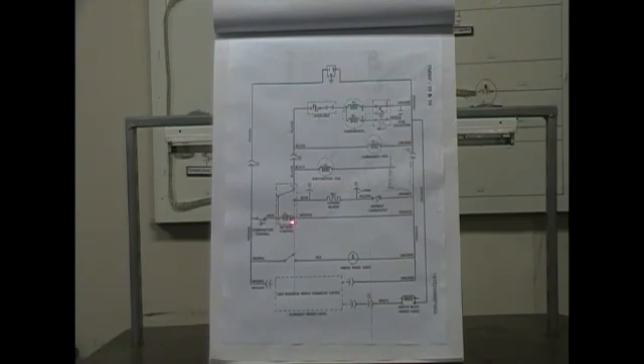Let's say your defrost control is turned into defrost mode. It will disconnect between 4 and 3, and it's connected between 3 and 2. So it turns off all these three components. It turns off your evaporator fan, condenser fan, and compressor. It only provides power supply between the blue wire to your defrost heater. And the yellow or pink wire connects to your defrost thermostat. And the other leg is orange wire going back to your common to complete the circuit. So that is your diagram for the refrigerator.